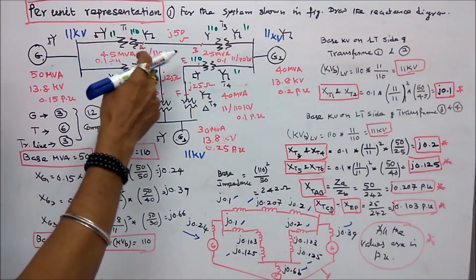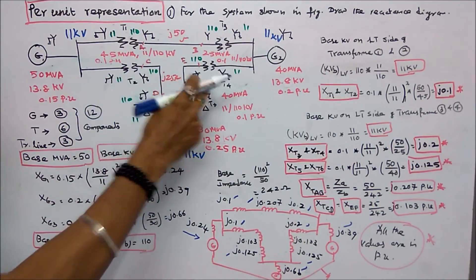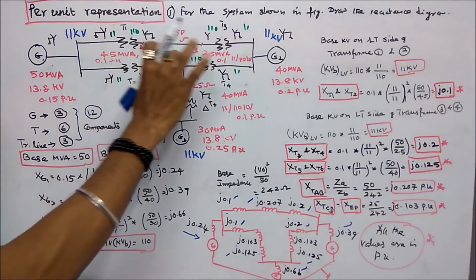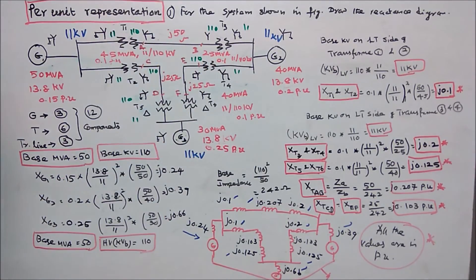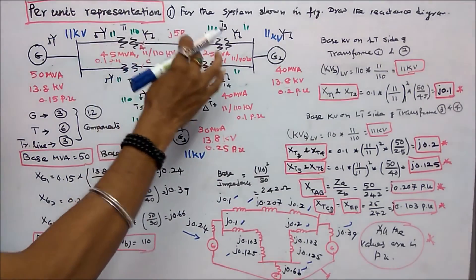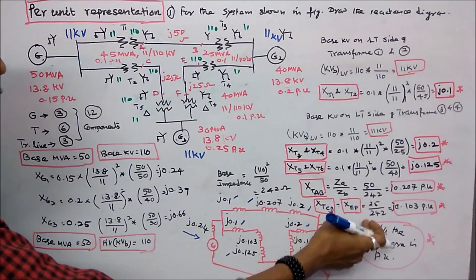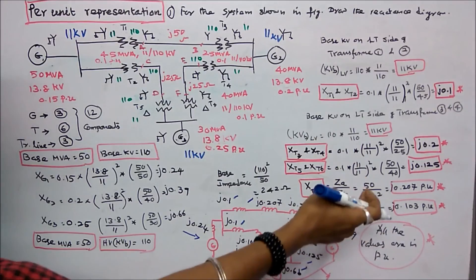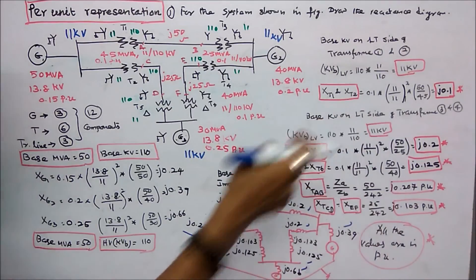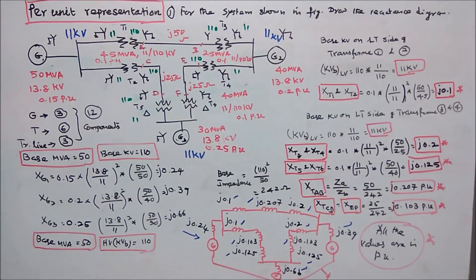Transmission lines CD and EF both have reactance j25 ohms, so their per unit values are the same. Per unit = 25 / 242 = j0.103. Both CD and EF are j0.103 per unit.